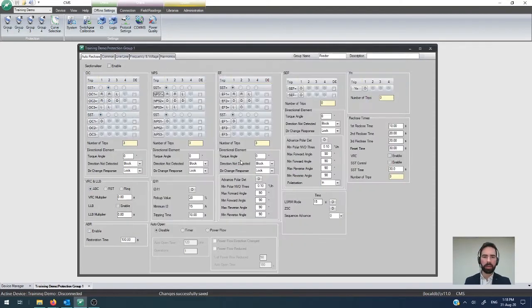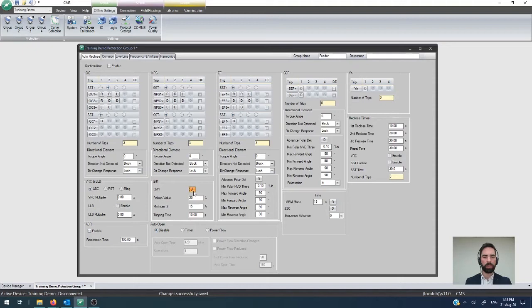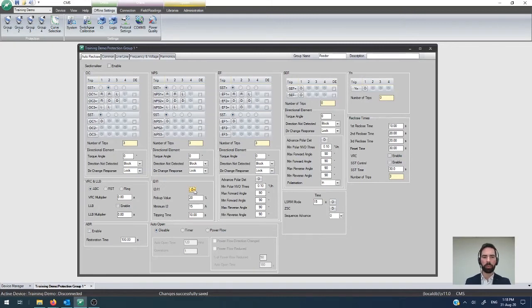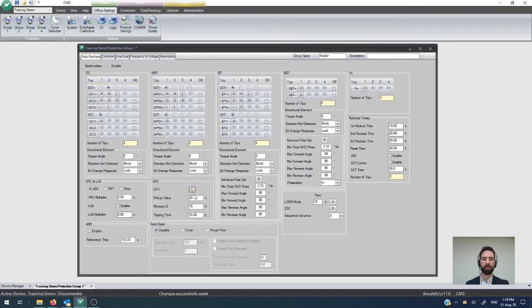For the i2 on i1 configuration, you don't have access to a reclose on that. Generally, if you have a broken conductor, that is not something that you want to try and mitigate with reclosing operations. Therefore, you either have the ability to alarm, which is something that I recommend if people haven't used this before and they want to get an understanding for what the network dynamics are, or if you've calculated that and you're very sure that you want to automatically lock out when you detect an i2 on i1 condition, then you can configure that to lockout.